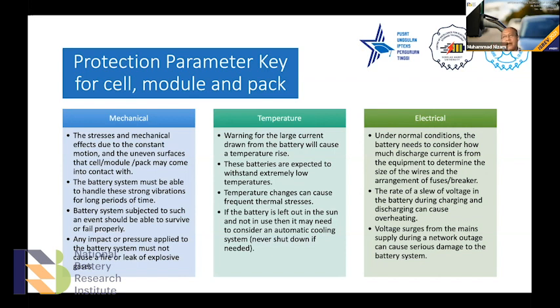This is for the battery energy storage system. During the outage, when the power system battery comes back on after outage, at the first step the surge amount is about 1.6 up to 2 times the capacity of the load. So can your battery handle that or not? These electrical parameters must be protected.